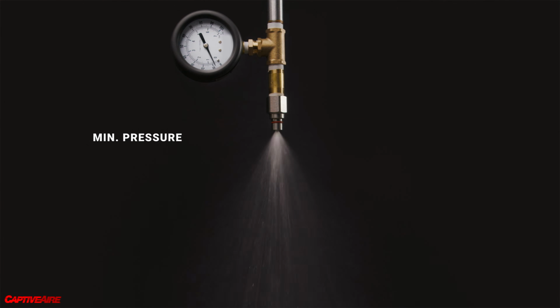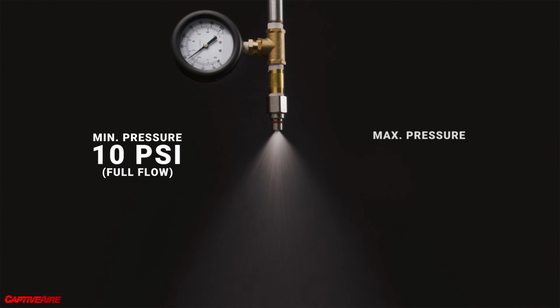When you're looking at especially the last nozzle in a system, you want to make sure you still have fully developed flow out of that nozzle. To do that, you have to start with a higher pressure, which will develop flow out of the nozzle. But you also don't want it too strong, or it will cause grease to splash everywhere when you hit it with the agent.